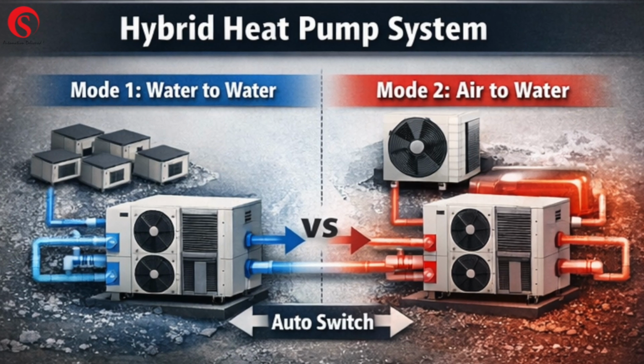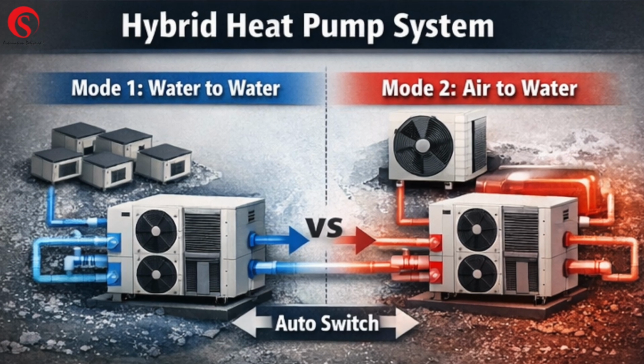In such cases, it will have to switch from water to water to air to water automatically using a hybrid system design. That is possible, and in my opinion, almost all the water to water heat pumps will have to be a hybrid heat pump to make this really work.